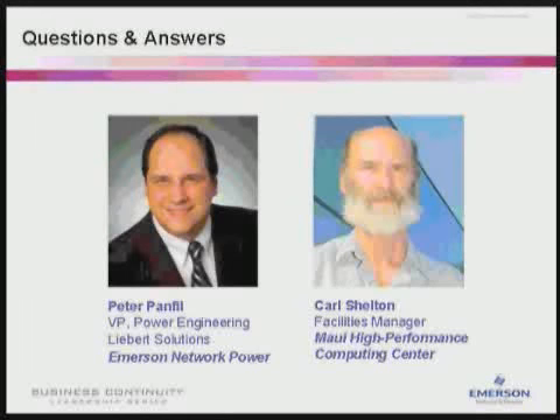Peter, back to you. This is from Steve, and he must be a freelancer as well. I see that the overhead XD works better than traditional units. What's your thought on this? The overhead XD unit has an advantage in that it is only dealing with the sensible heat that's being produced right there at the top of that cold aisle. And so it doesn't have to deal with that base level of cooling and air filtration and humidification management that you heard Carl talk about in his presentation.